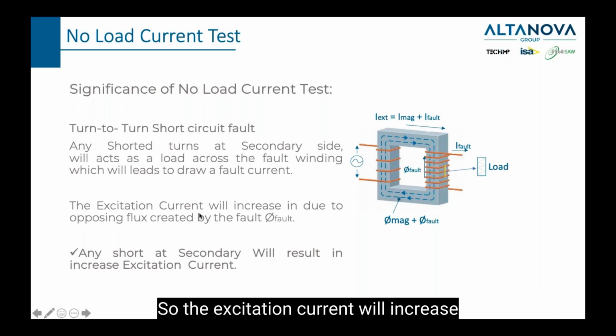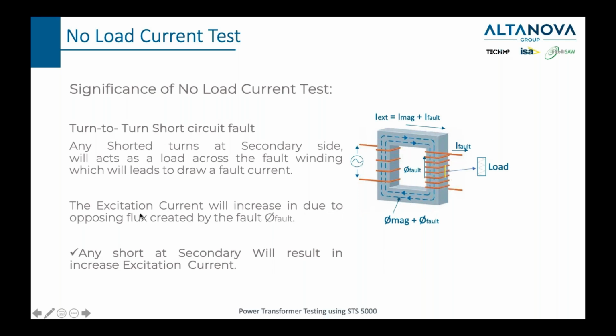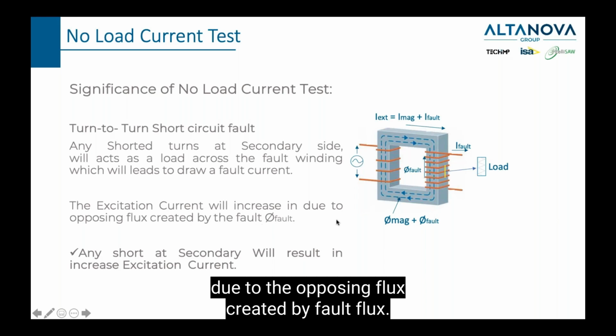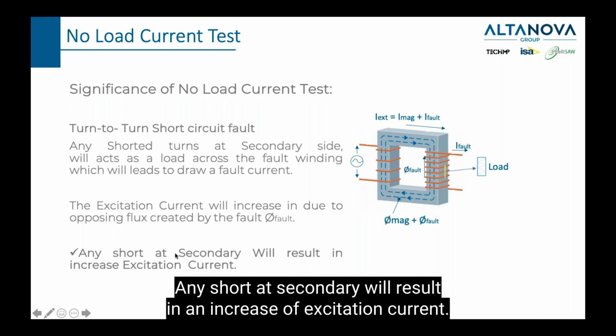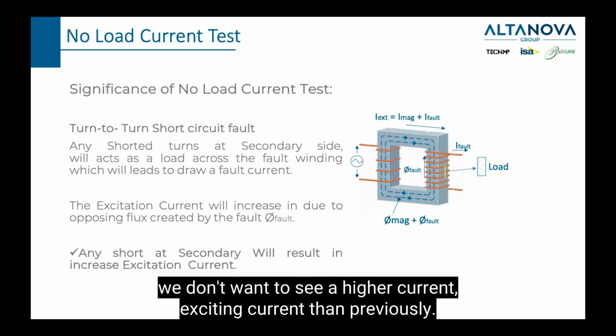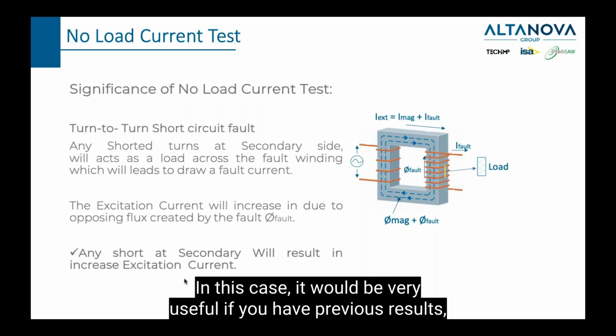So the excitation current will increase due to the opposing flux created by the fault flux. Any short at the secondary will result in an increase of excitation current. Long story short, we don't want to see a higher excitation current than previously.